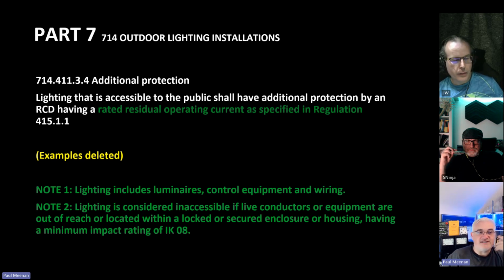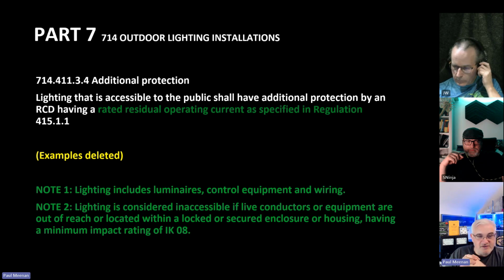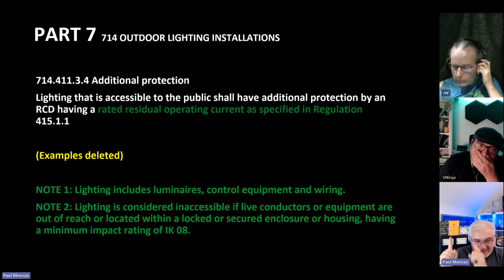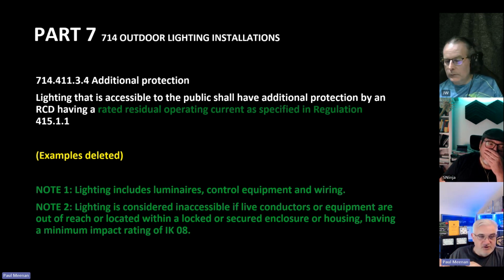714.411.3.4: lighting that is accessible to the public shall have additional protection by an RCD, which is a current reg, but they've added having a rated residual operating current as specified in regulation 415.1.1. The examples have now been deleted from that regulation, but two notes have been added. One says lighting includes luminaires, control equipment and wiring - don't really know why they needed to define that, but okay. Note 2 says lighting is considered inaccessible if live conductors or equipment are out of reach, or located within a locked or secure enclosure having a minimum impact rating of IK08.